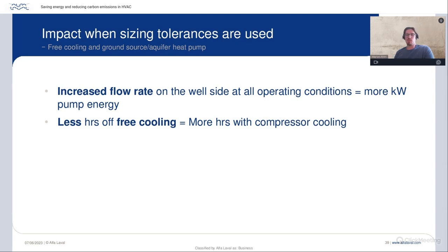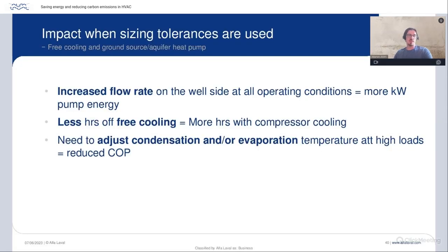If you have temperatures in your bedrock, as in this case, so that you can actually use it as free cooling, that also means that the capacity has a limitation, which means that you will have to operate the heat pump or chiller, adding on compressor cooling, more hours of the year. So that's also increased energy consumption, of course. And then sometimes you would reach the maximum capacity of the heat pump or chiller, and to compensate for that, you will have to reduce the evaporation temperature or increase the condensation temperature, which then influences the COP of the heat pump or chiller negatively as well.